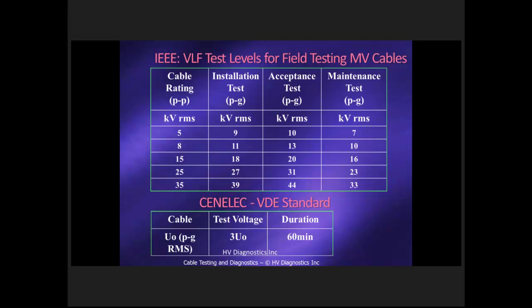That means when you're testing a cable and you want to make sure it is partial discharge free, you want to make sure that it's partial discharge free up to 16 kV if it's an existing cable, or up to 20 kV if it's a new cable, and we're talking about a 15 kV rated cable in the same situation. And the same would apply if you're dealing with 25 kV or 35 kV cable. The standards for the international European community use 3 times operating voltage, RMS phase to ground operating voltage, and their duration is 60 minutes. We have a slightly different standard for IEEE.